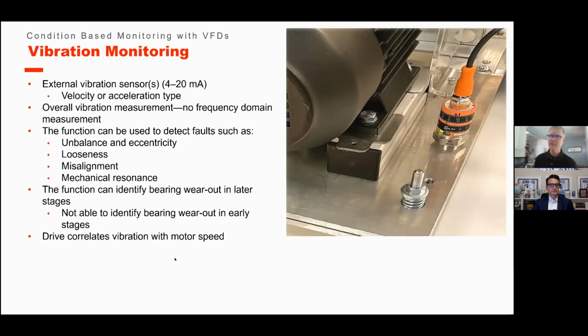Drives correlate the vibration with motor speed. We just kind of covered that. There are speed ranges where resonance happens. It's the nature of balance, and it's the nature of the way machines are put together mechanically. It happens, especially in HVAC. One point I love to bring out about this type of software, this embedded software in a drive, is that it's permanent monitoring. It's 24/7 versus occasional service checks.